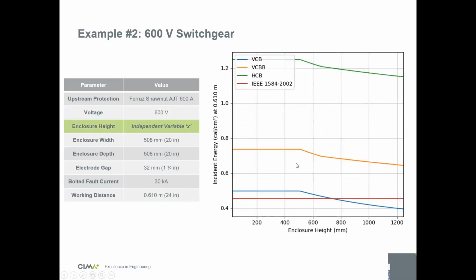So let's look at other parameters. Let's say your height. Your height doesn't have that much impact. You see it goes from above 1.2 to below 1.2, so it's not that much. But still, if you're above 1.2, you need more PPE to do live work than if you're below 1.2. PPE is personal protective equipment, so height can have an impact on whether you need a face shield or not. Still, your worst-case energy is at lower height, and it goes down when you increase the height.